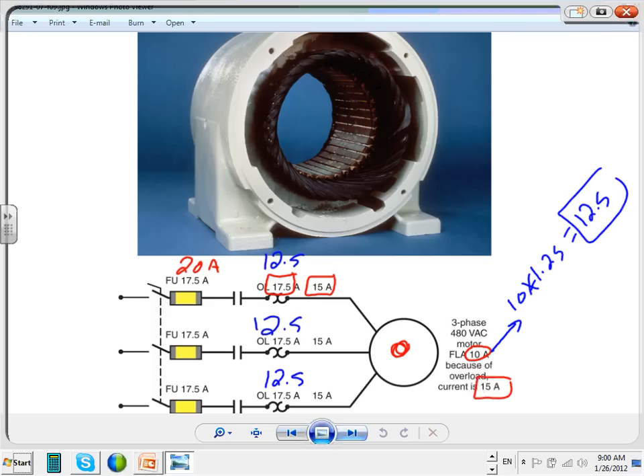No, the same example that we did. It was 20 before. The same picture. The current times 1.25. I take 10 and multiply it by 1.25. That's for the conductor. For the fuse, you guys remember how we size the fuse? We size the fuse, if it's a dual element time delay fuse, based on 1.75 times 10, and that will give me 17.5 amp.